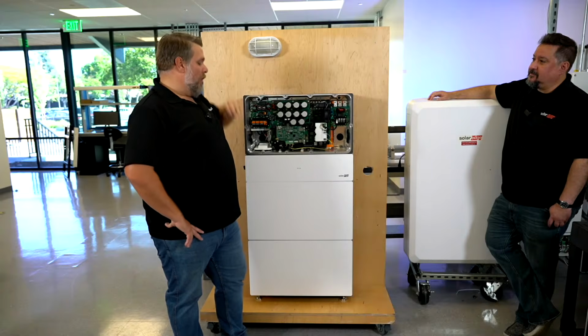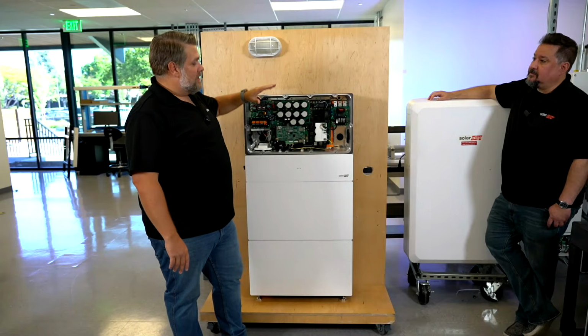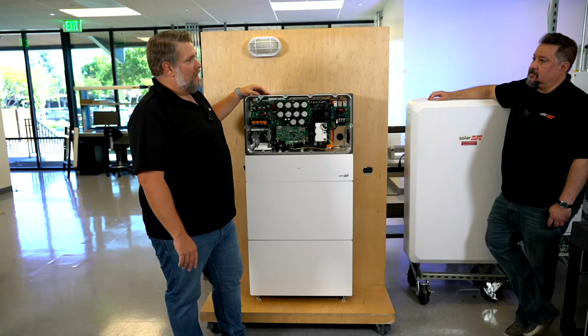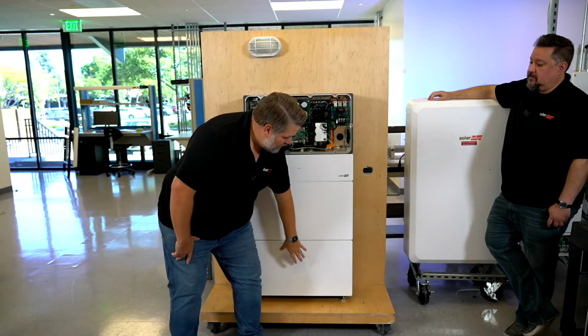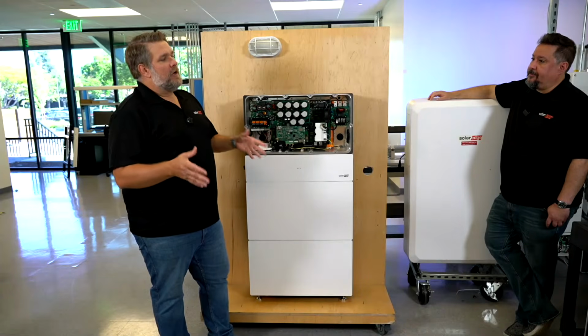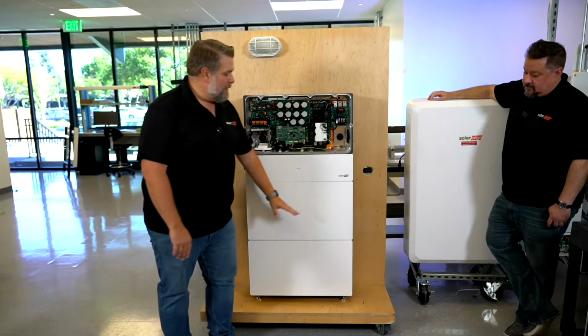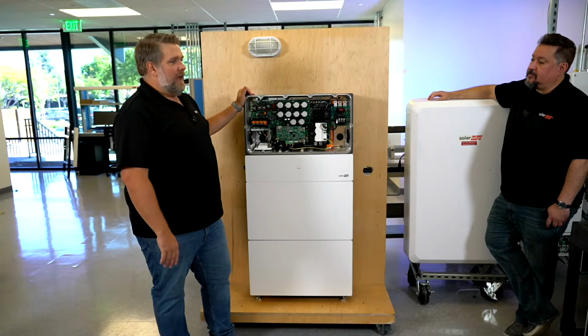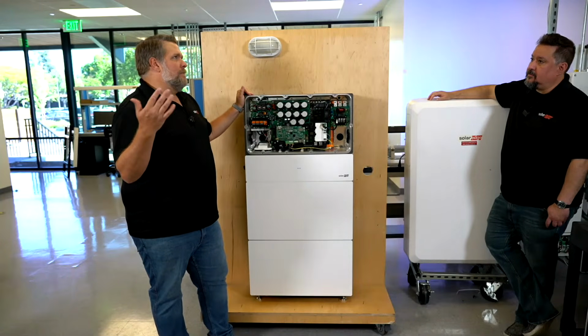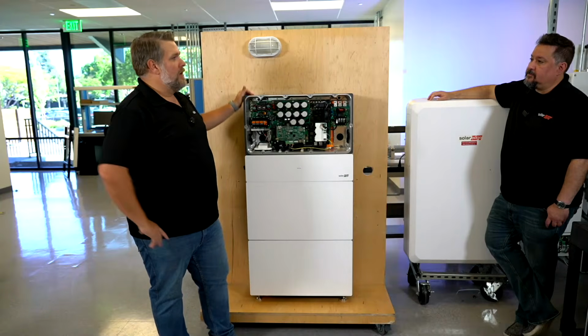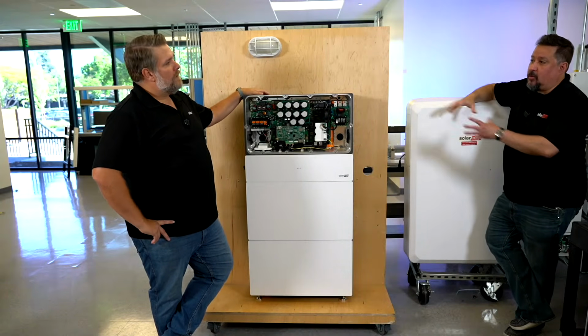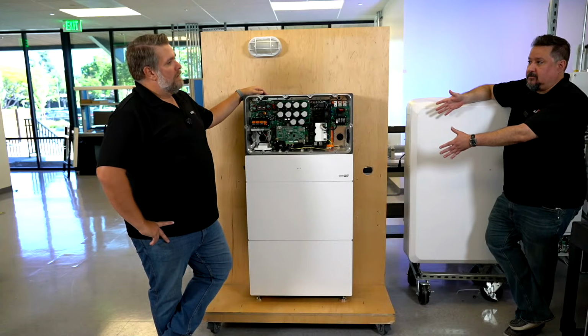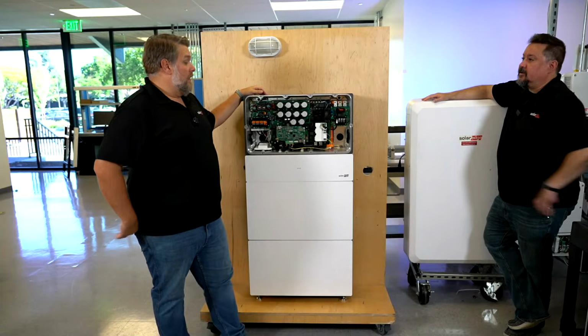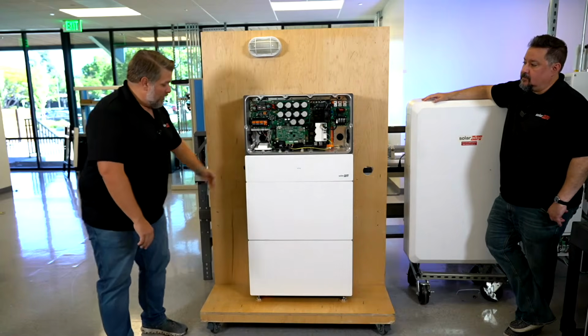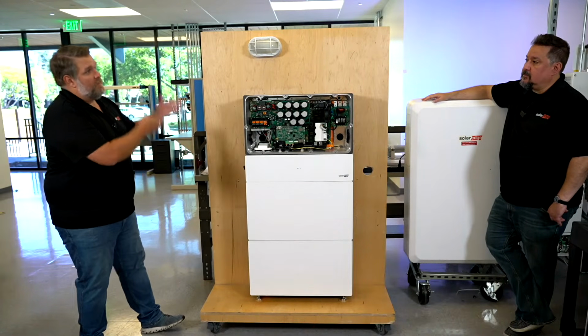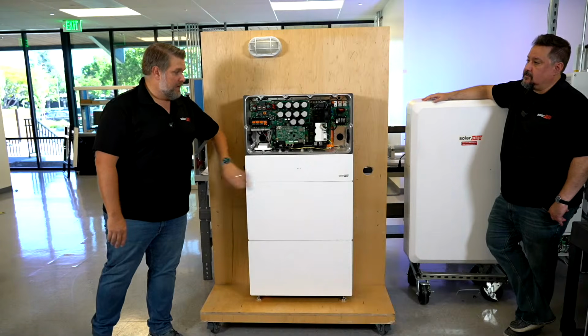So if you do a wall mount with 4 battery blocks, a link, and a Nexus inverter, your wall mount only allows the battery to be 2 inches off the ground. But I don't think many people will do that. Most people will probably do 3 battery blocks as the most common configuration, putting it around 30-something inches off the ground and still under 6'7". Later on, if you wanted more battery capacity, you could just set another battery and link next to it, or in front, or to the side 4 inches apart, and do another stack of 2, 3, or 4 battery blocks and connect the links together.